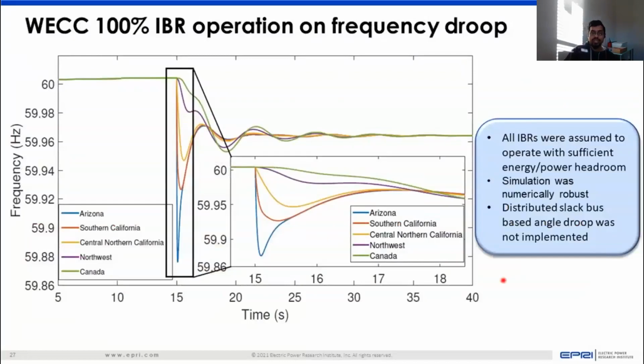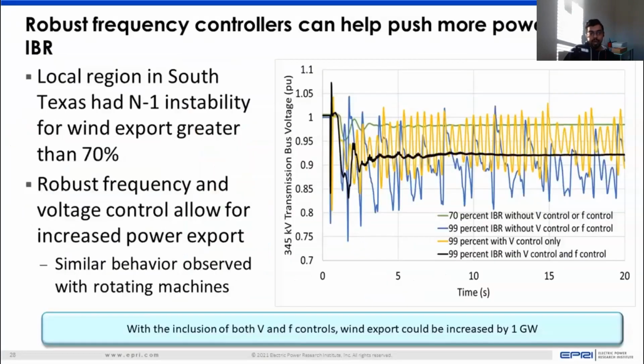And for that 160 gigawatt network, for a 4% load increase that occurred, which is their regular planning criteria, assuming all inverter-based resources have sufficient headroom, you can get numerically robust results and a scenario where you have stable frequency response across the network, if the inverter-based resource controls are tuned or designed or located in an adequate location.